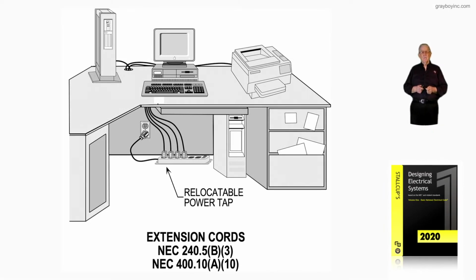This illustration still deals with extension cords, but we're reviewing the sections 240.5(B)(3) along with 400.10(A)(10). Now, notice I might have 10 outlets, duplexes, on a 20 amp circuit. Now, a duplex has 2 plug-in areas. So that would allow you to plug in 20 things.